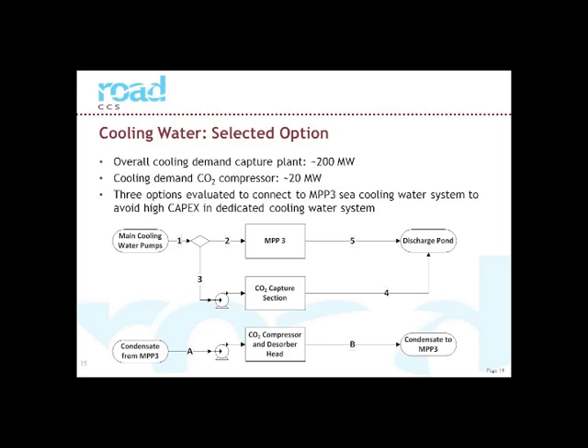We evaluated 3 options to make the connection to the MPP3 cooling water system. We have decided not to build a separate cooling water system to avoid high capital expenditures, but we extract cooling water from the supply line to MPP3 and dump it in the discharge pond I've shown on the picture before.